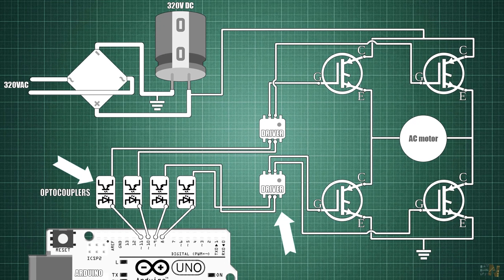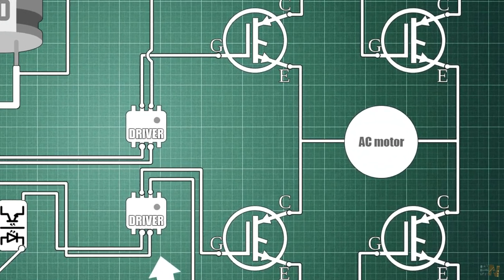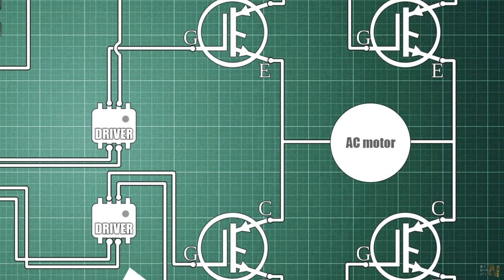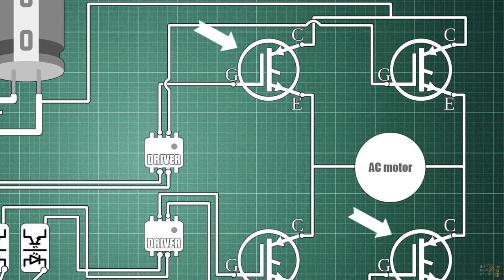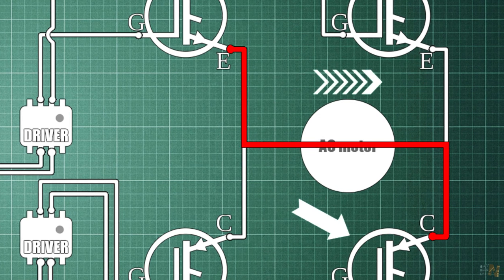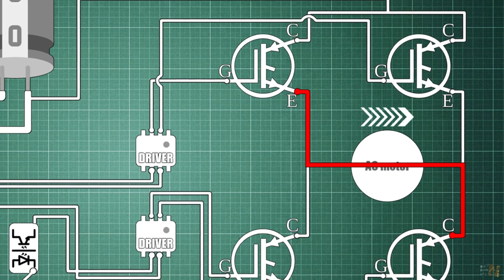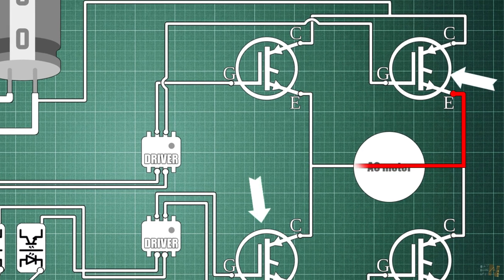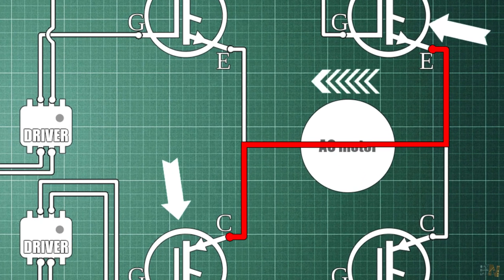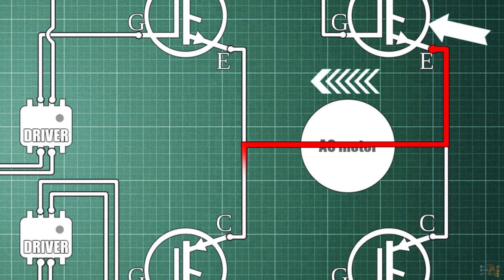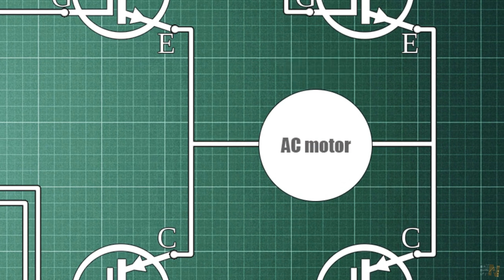As you can see, the load, in this case the AC motor, is connected in the middle of the H-bridge. When we enable these two transistors, those 320V will pass from this side of the motor to the other side, creating a magnetic field in one direction. Now we turn off these transistors and enable these other transistors. So now a current will flow in the opposite direction, so the magnetic field is now reversed. If we switch these transistors on and off, in this way we can create an oscillating AC signal of high voltage.